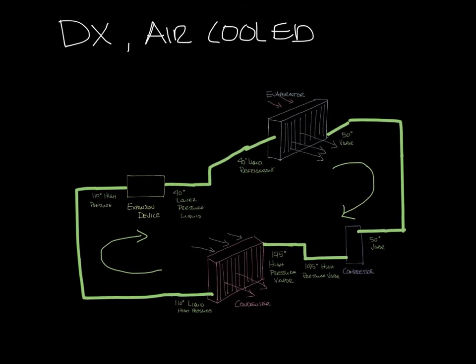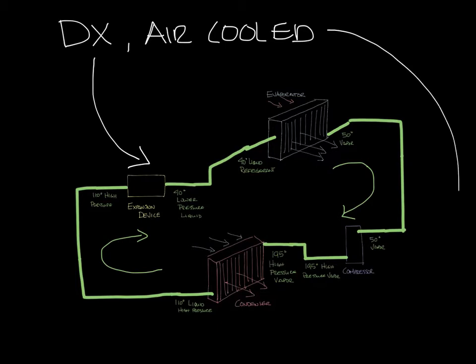What I drew out last week was a DX air-cooled system, so let's bring that back up. It's called direct expansion because we use the expansion and compression of the refrigerant to produce cooling, and it's air-cooled because we used a fan to draw air across the condenser to cool the refrigerant.